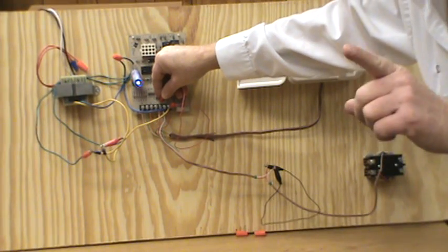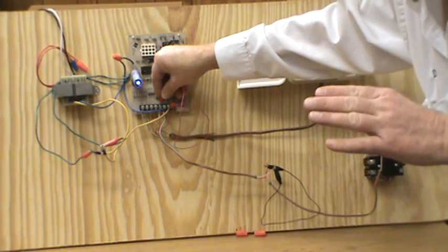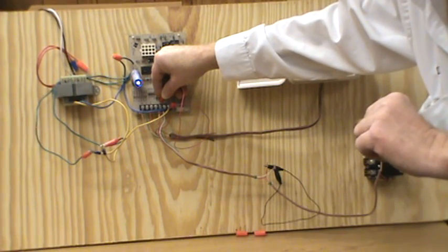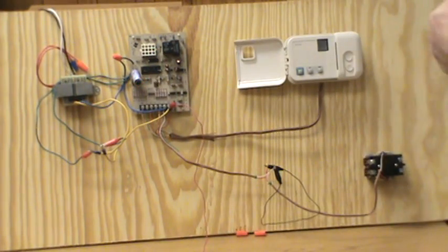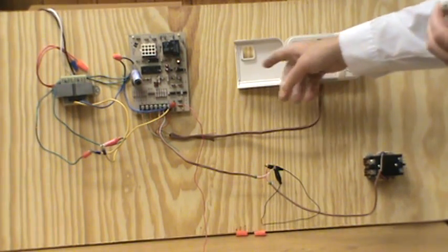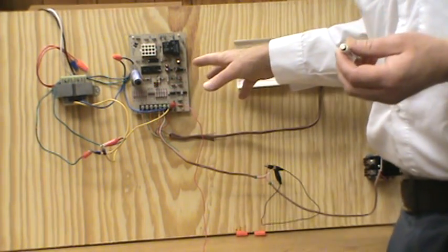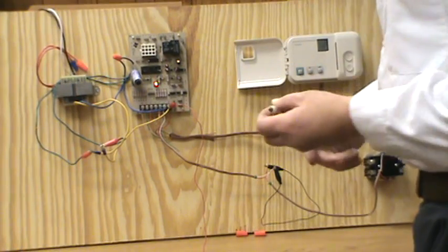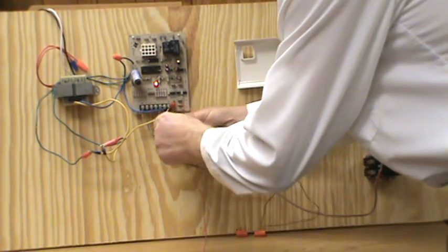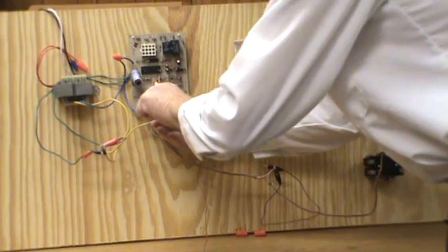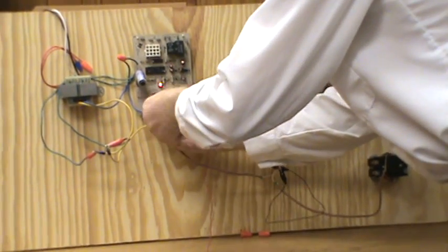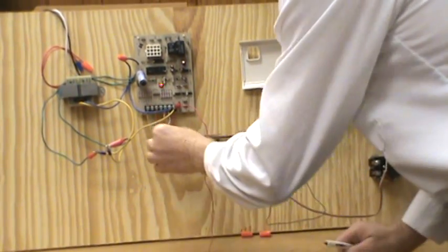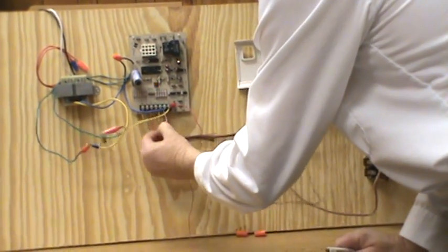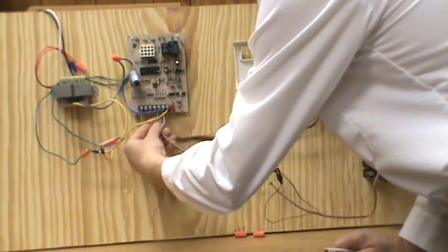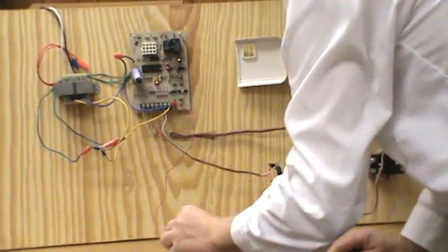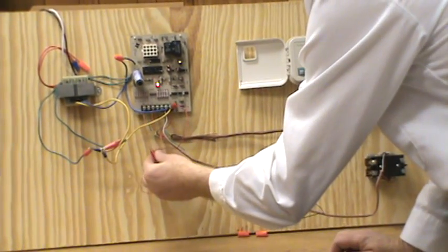So now that we've located which branch circuit has got the short, we want to isolate it, because it could be the wire going to the thermostat on the cool circuit. It could be something on the circuit board. Y terminal has a default or fault condition inside the circuit board, or is it the wiring going outside? So what we're going to do is we're going to separate the two wires that went to the cooling circuit, and then we're going to pinpoint which part of the circuit's got the short.